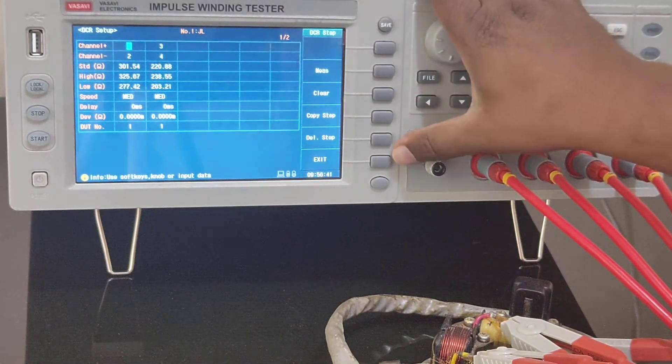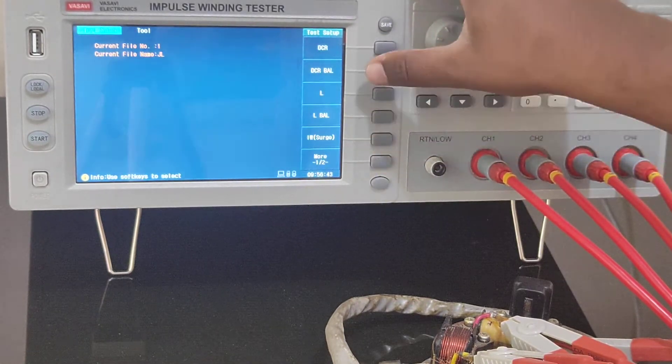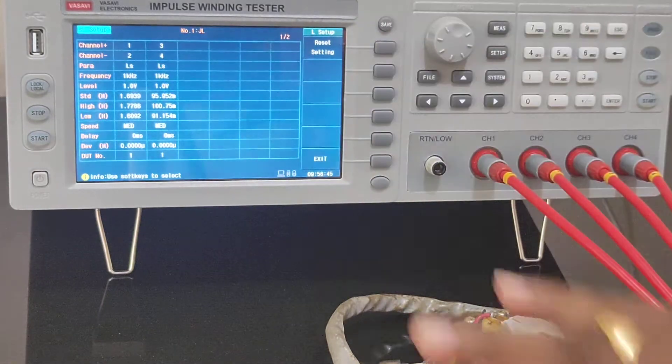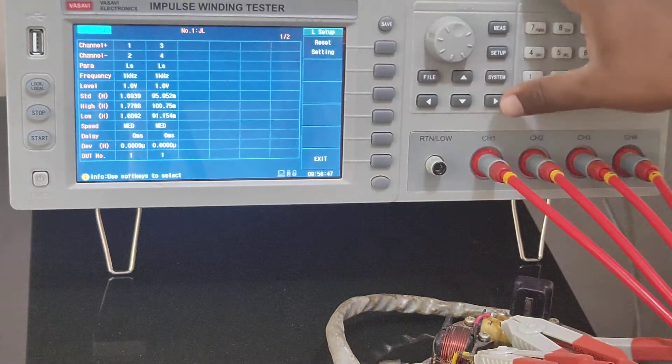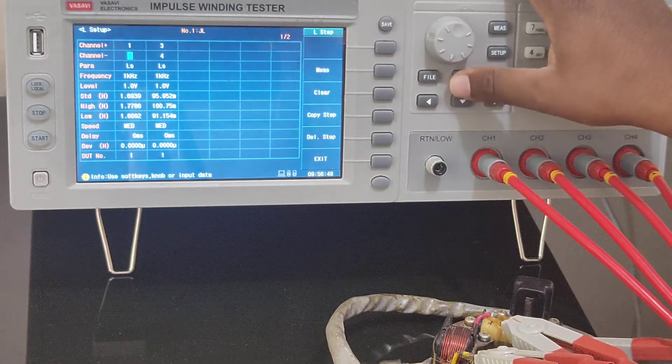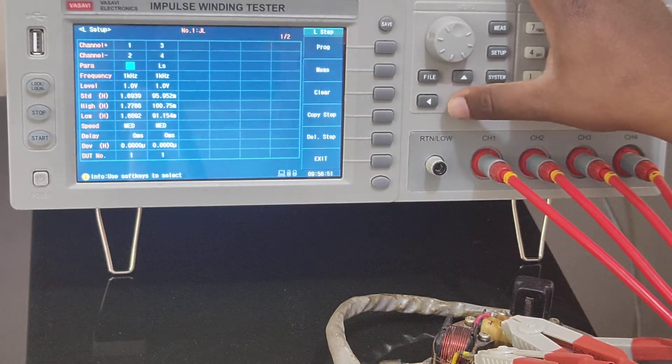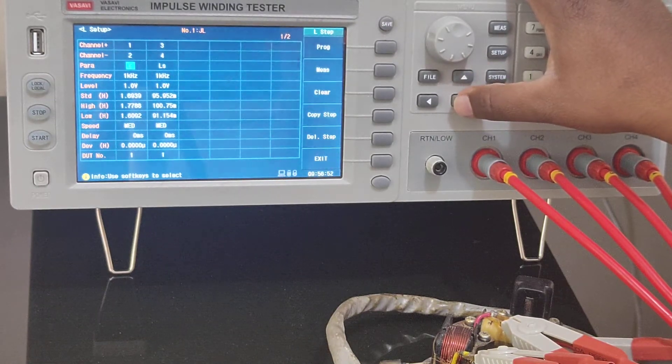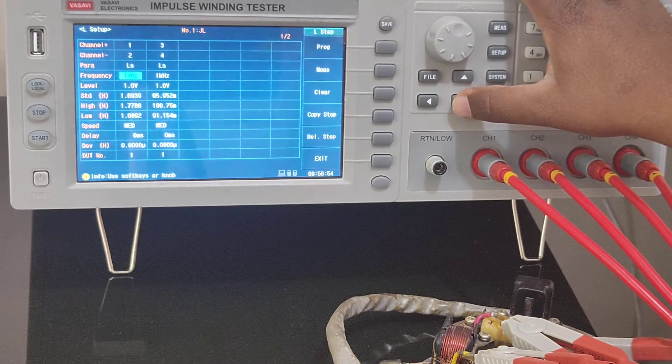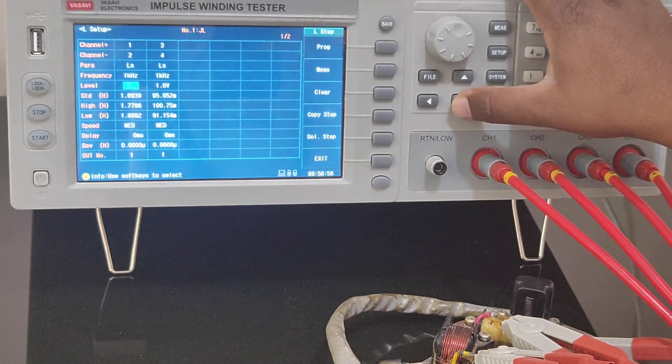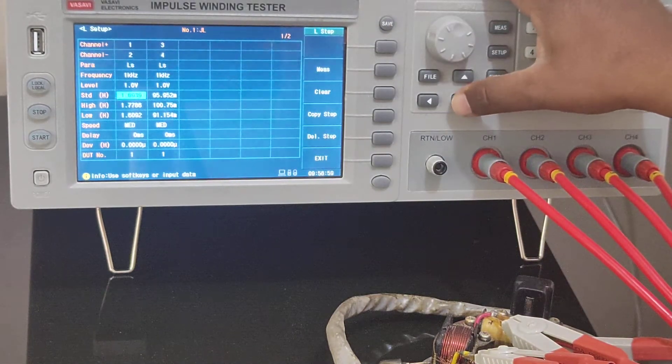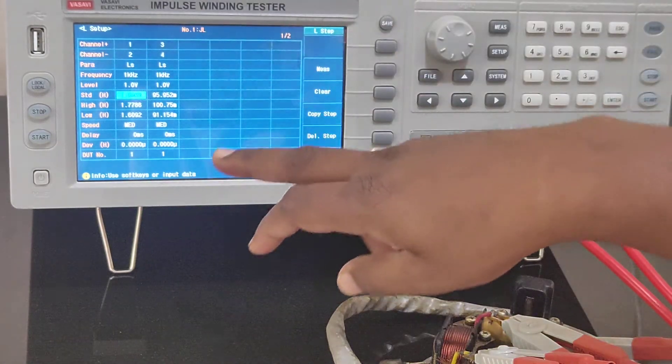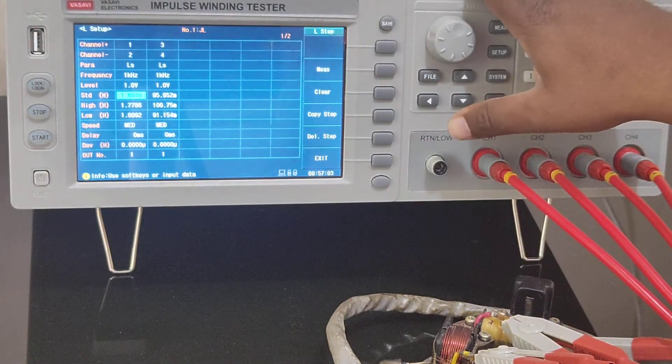Now I'll show you inductance. It's the same way, only thing is the parameter changes. This is between channel 1 and 2. This is inductance - at what frequency you want to measure, and this is the test voltage.